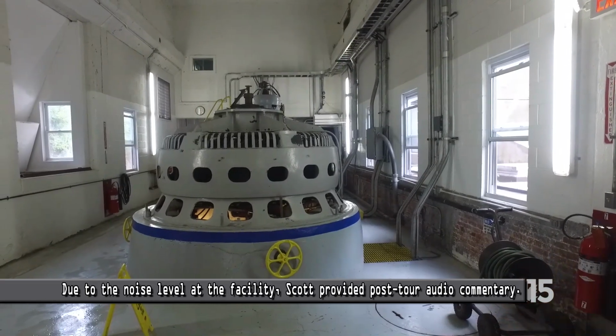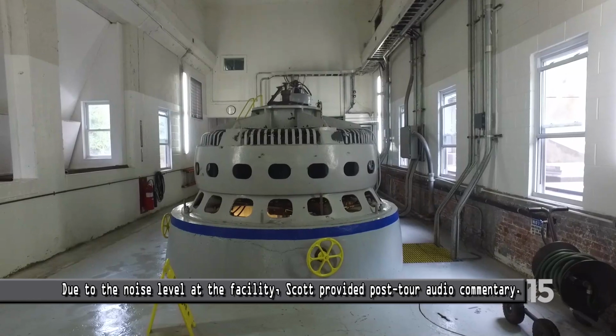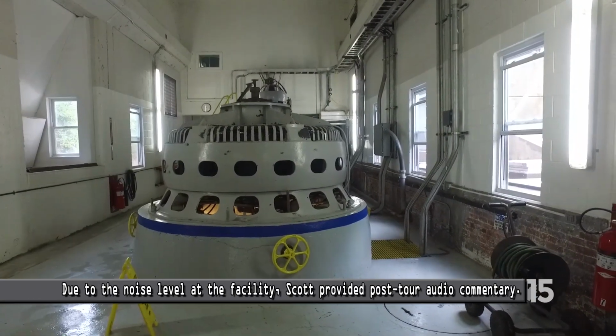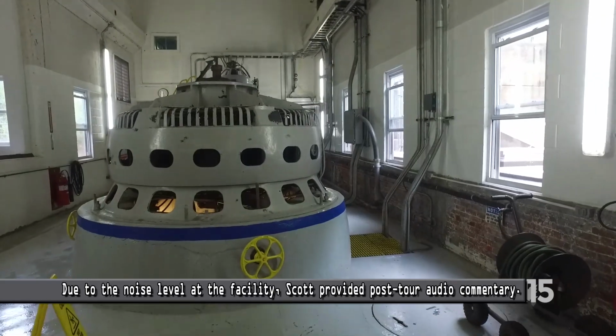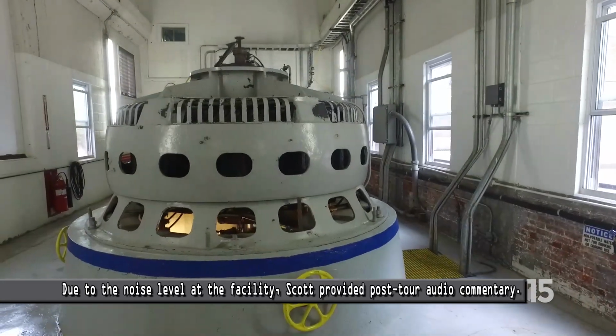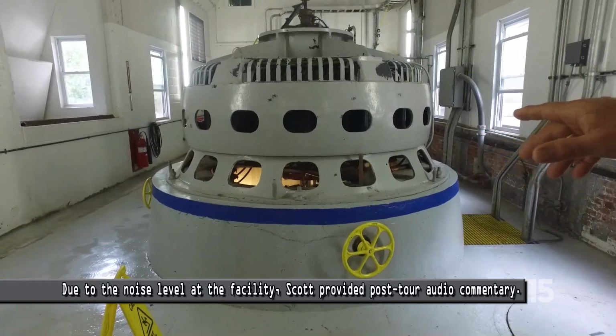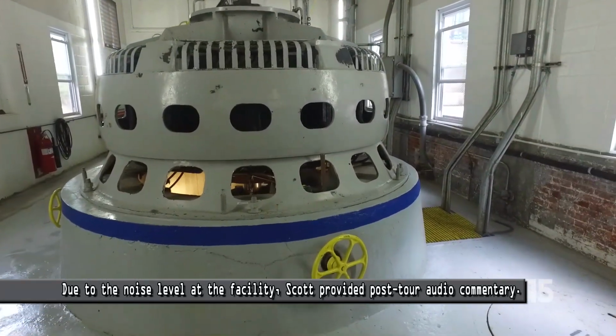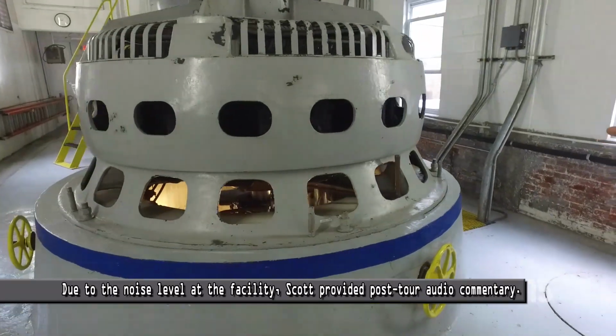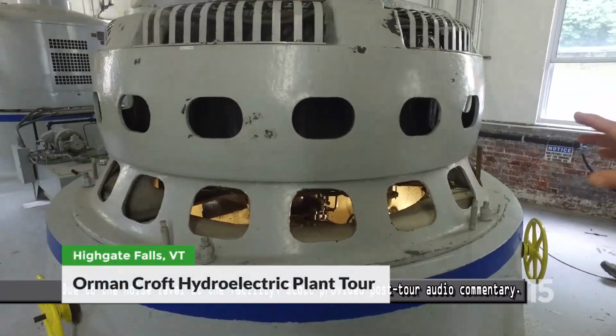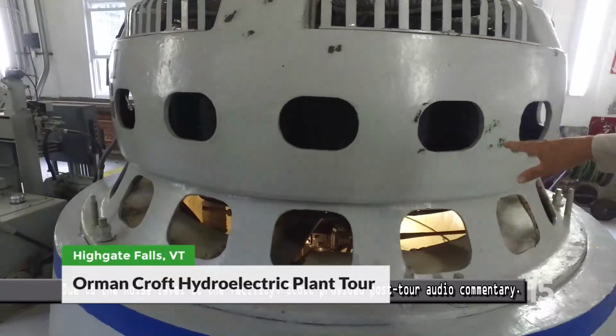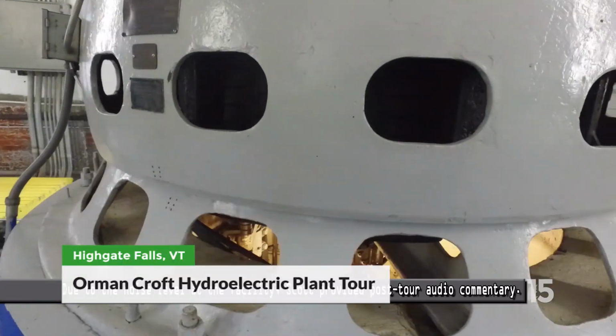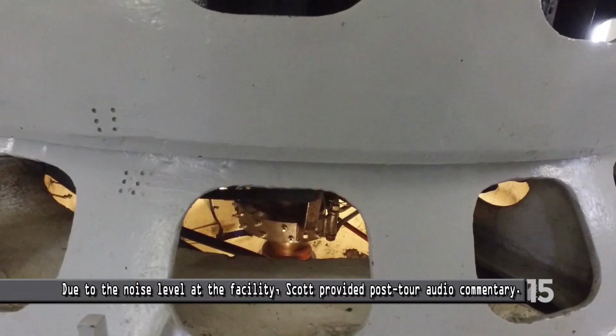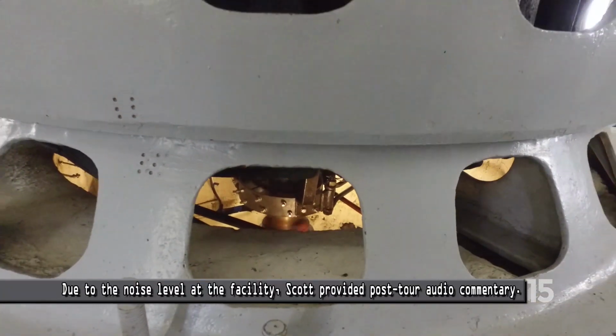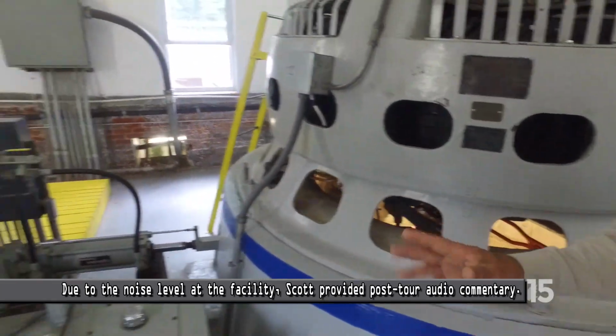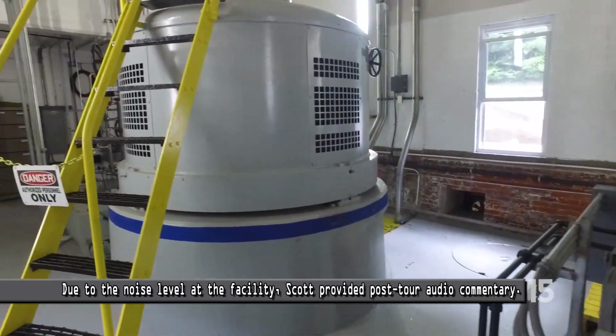Installed in 1928. Capacity of, I believe it's on a good day, 1.2 megawatts. It's operational at this time. We are at minimum flow, and we run this unit at this time because we don't require any auxiliary power to run pumps and filters. There you can see the shaft spinning. You got the HPU and the governor.